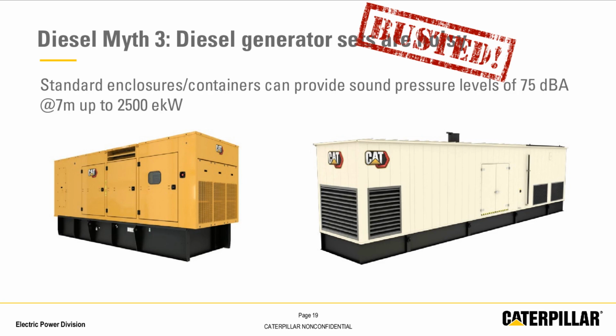These can emit sound pressure levels as low as 75 dBA at 7 meters, even on large sets right up to 2,500 kilowatts. So a lot can be achieved in noise reduction using these sound attenuating enclosures, and generally it's a balance of performance versus cost. You can get even lower sound pressure levels than 75 dBA at 7 meters, even on larger gensets. So with that, the myth is busted.